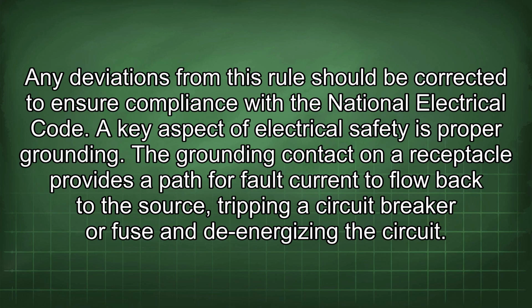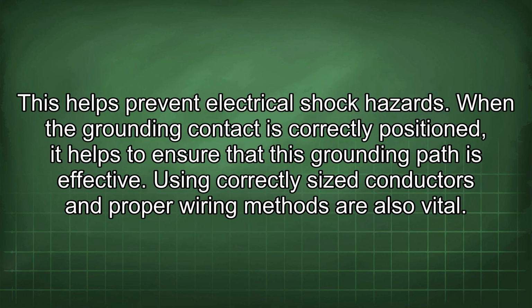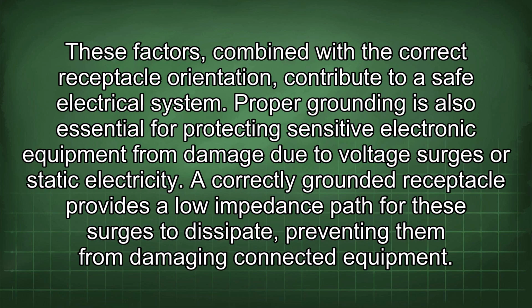A key aspect of electrical safety is proper grounding. The grounding contact on a receptacle provides a path for fault current to flow back to the source, tripping a circuit breaker or fuse and de-energizing the circuit. This helps prevent electrical shock hazards. When the grounding contact is correctly positioned, it helps to ensure that this grounding path is effective. Using correctly sized conductors and proper wiring methods are also vital. These factors, combined with the correct receptacle orientation, contribute to a safe electrical system.